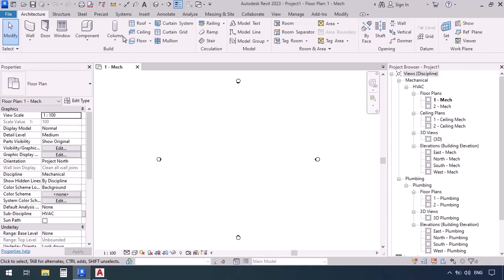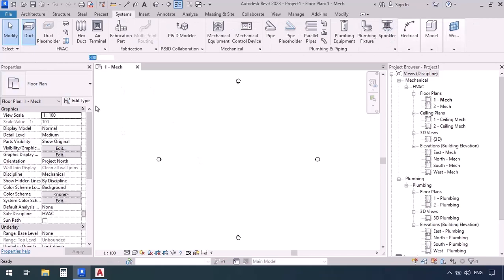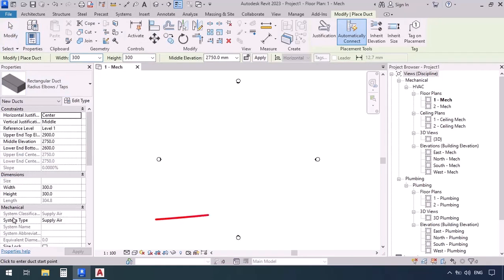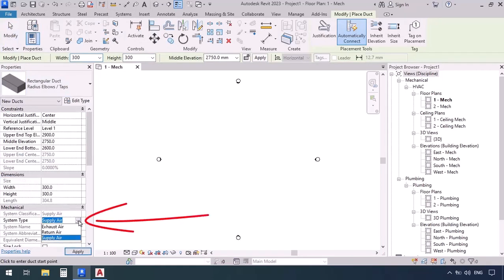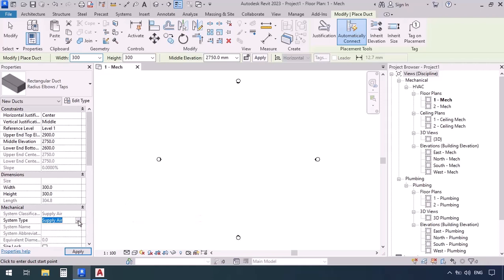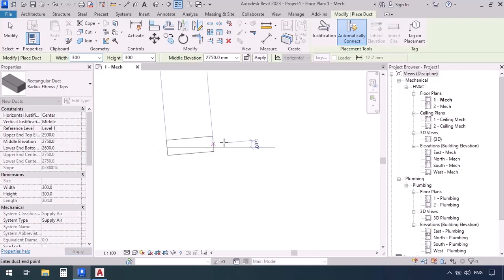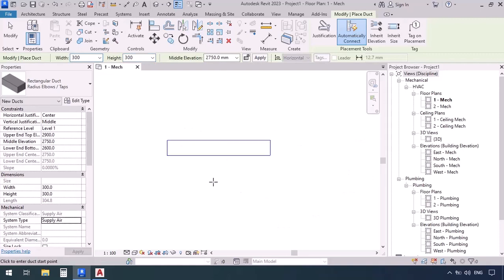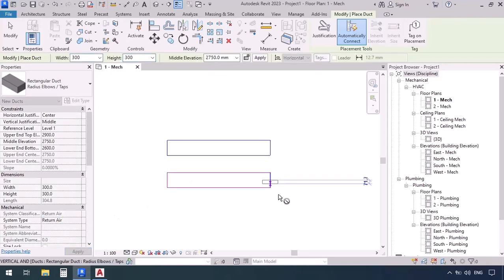To set the system type, go to the Systems tab and activate the Duct command, then select a fitting type. In the Properties window, open the system type dropdown and you can see exhaust, return, and supply. By default it is set to supply, so in all previous videos we have been drawing ducts as supply. For example, click and click and escape — supply is drawn in blue. Now drawing one with return — click, click, escape — return is shown in pink.